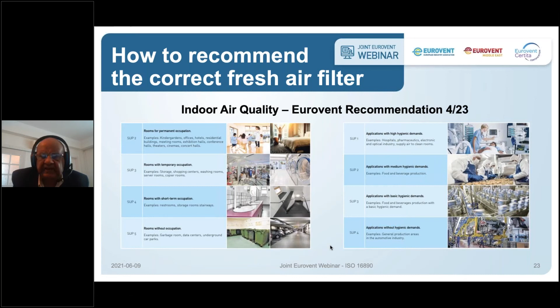Now the filters get nicely tied up with the outdoor air quality and indoor air quality - a tool to select the correct filter with the right pressure drop and have the right amount of energy spent because of the pressure drop in the filters. They reflect different values going from the everyday filter to the highest quality and highest priced filter, showing the energy efficiency difference. That's going to be very helpful in keeping filtration levels and energy efficiency going together.